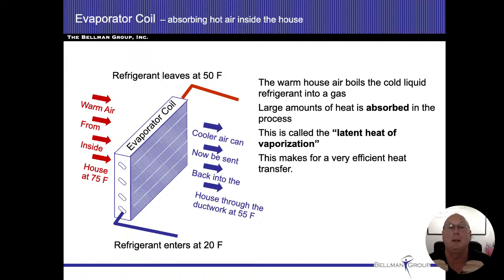The heat that's being absorbed is called latent heat. And we're going to refer to this process as latent heat of vaporization. When we're discharging the heat, as we're changing state, that's a latent heat of condensation. And again, it does make for a very efficient heat transfer.